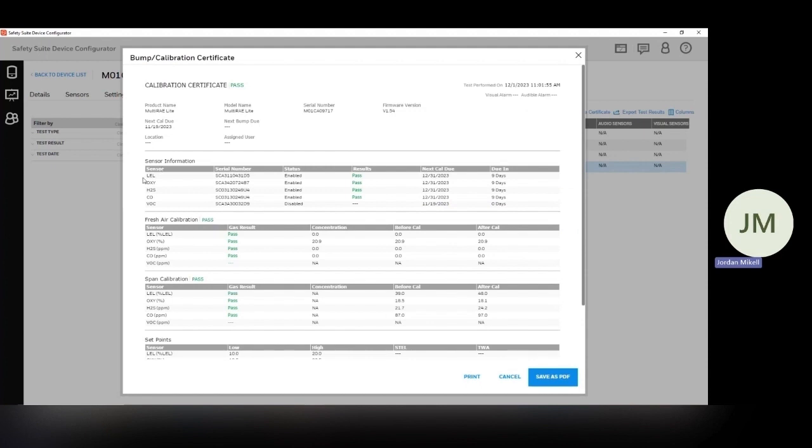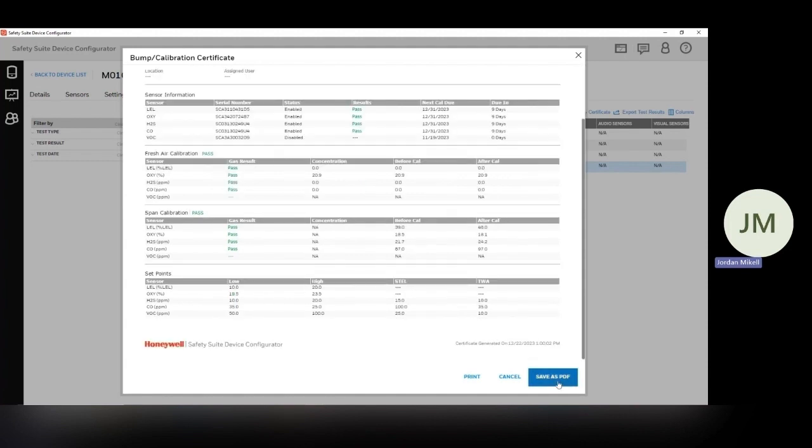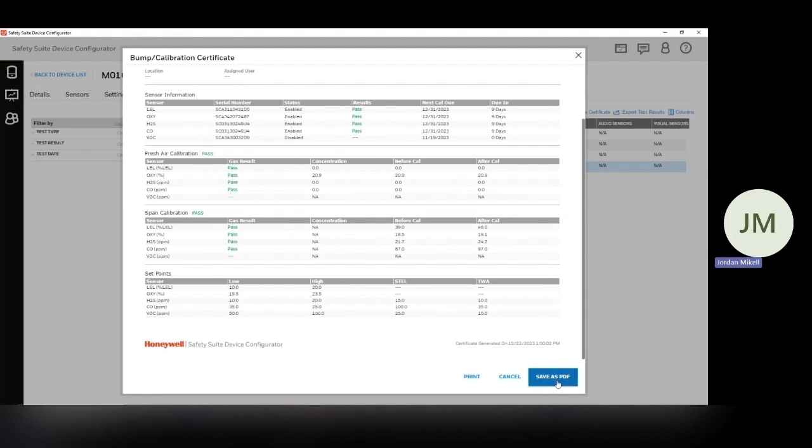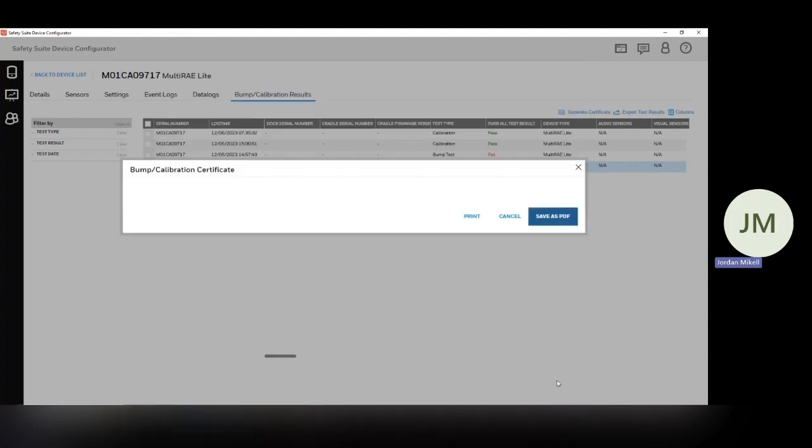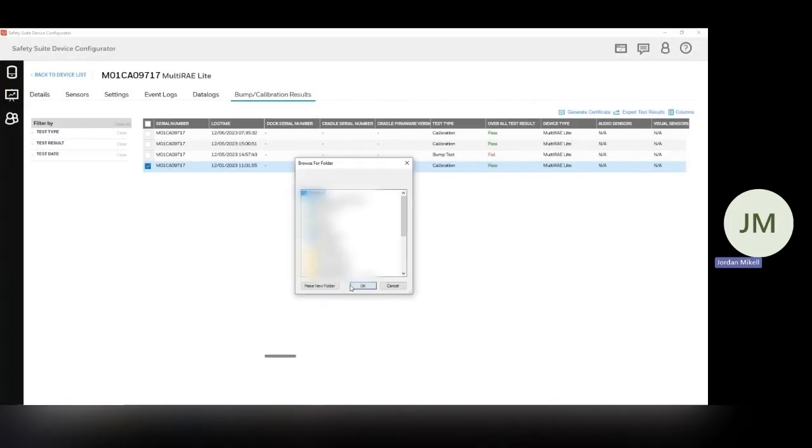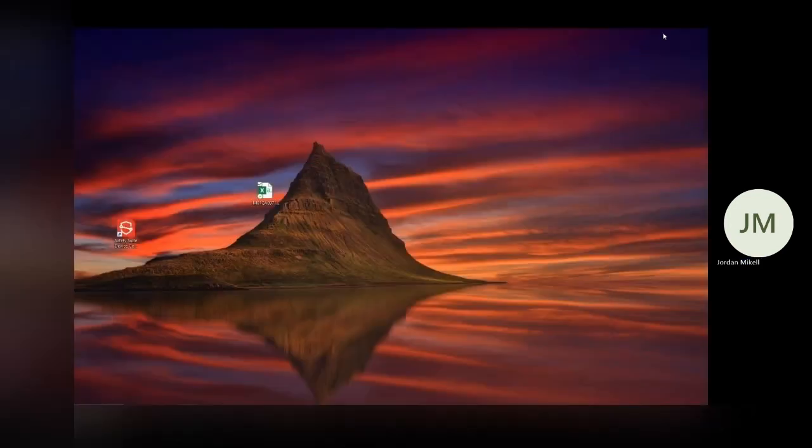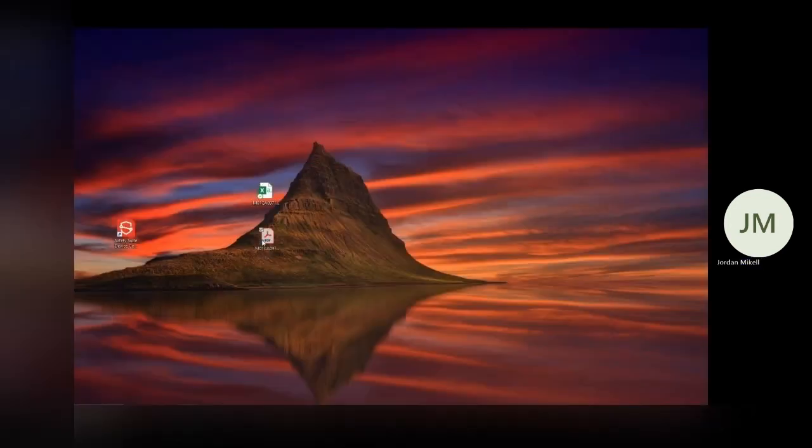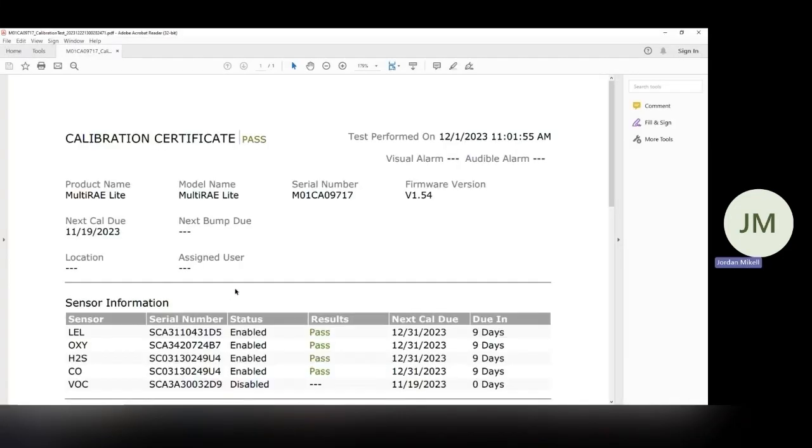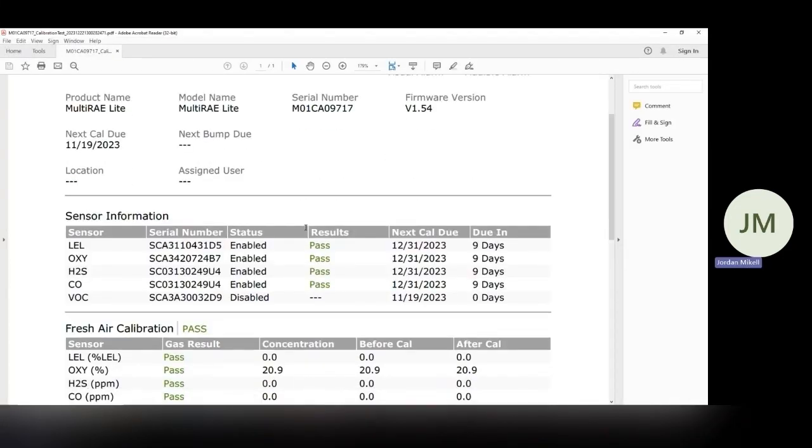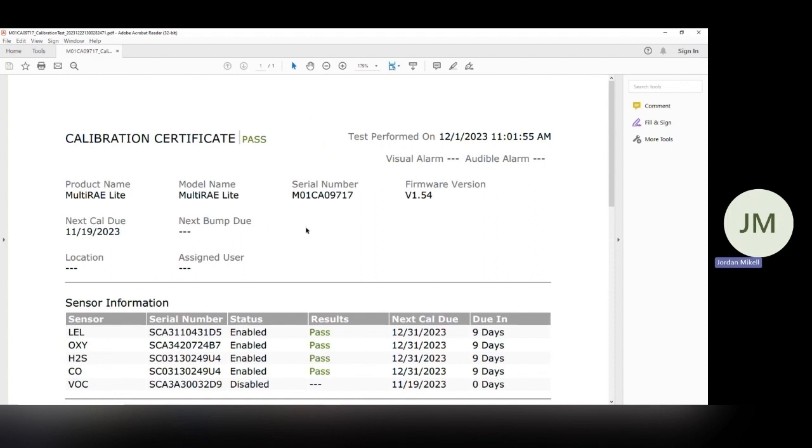You get all the nice details, the serial number of the sensors, whether or not it passed or failed, the adjustments made during that calibration as well. So we had some decent adjustments here and then we can just save it as a PDF. So same thing with this, I will save it to my desktop. And there's my PDF of the calibration certificate. So just a few easy steps. You can download the data from your instrument and also get a calibration certificate to save for your records.